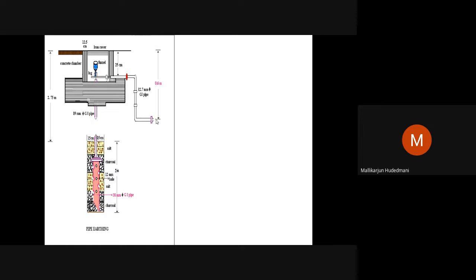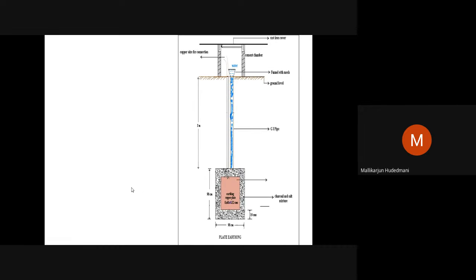So what you are supposed to remember is one rough sketch of this kind, a pipe of 38 mm diameter, a pipe of 19 mm diameter, a depth of 2 to 2.75 meters, a chamber, and a drawl of this cable to the meter box. Alternate layers of charcoal and salt for a depth of 15 centimeters should be there. That comes under domestic earthing for premises.